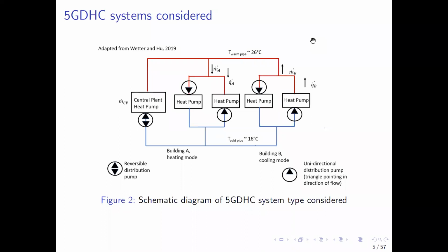In that, if Q dot A here, or the load assigned to building A, is perhaps opposite in nature of Q dot B, meaning that building A is in cooling mode while building B is in heating mode, the combined heat and heat rejection draws from each of those buildings can offset the load on the centralized heat pump and improve the energy efficiency of the system's performance. And this characteristic of the systems both complicates their design and also creates an opportunity for potential savings from network topology optimization.